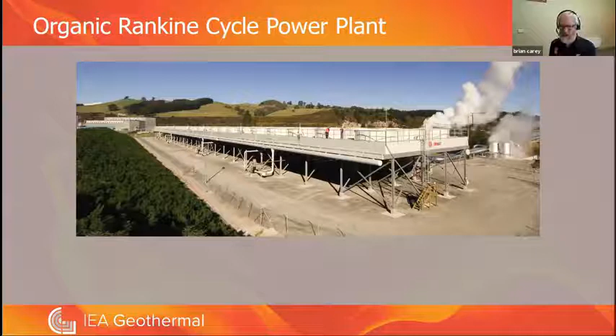So how do these organic Rankine cycle plants work? Well, you have heat coming into heat exchangers, which basically heat an organic working fluid that is a liquid phase, takes it through to a vapor phase. That vapor, organic vapor, is expanded through a turbine, and that vapor is then taken through a condenser, condensed back to liquid, pumped back up to the pressure conditions of the heat exchange equipment and the vaporizer to repeat the cycle. So the organic fluid goes round and around the cycle and is not used up in the cycle, and the heat is basically taken from the geothermal fluid flow, whether it be steam or water. So the incoming geothermal fluid is cooled, goes out cooler, and this heat is transferred to the organic vapor.